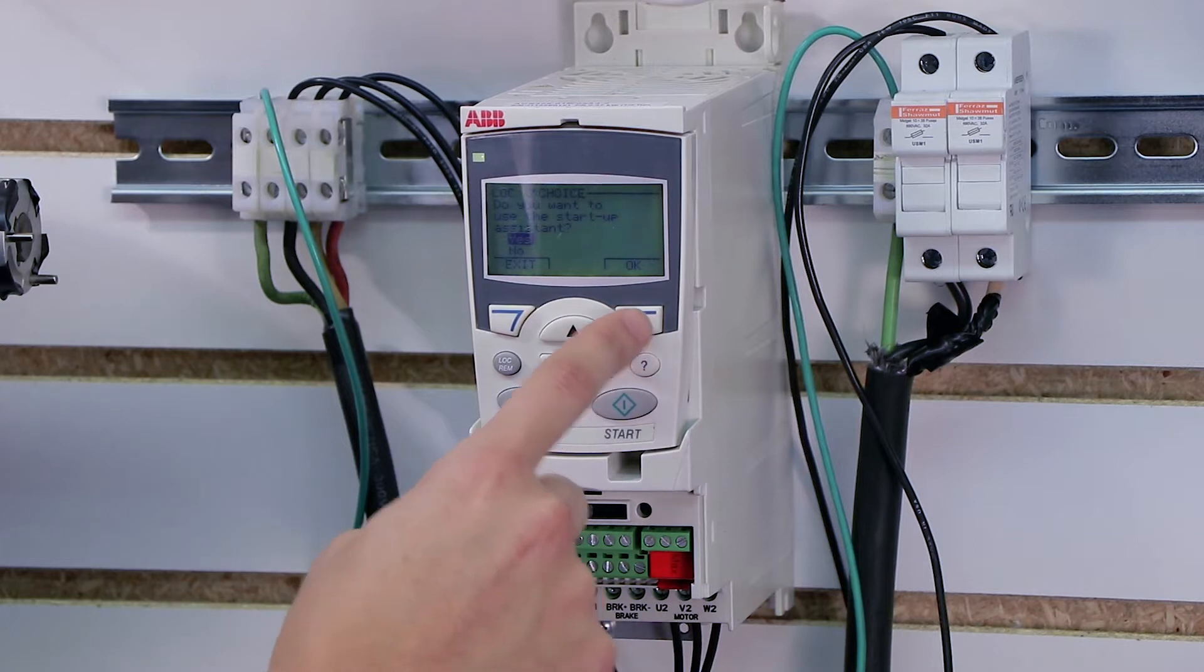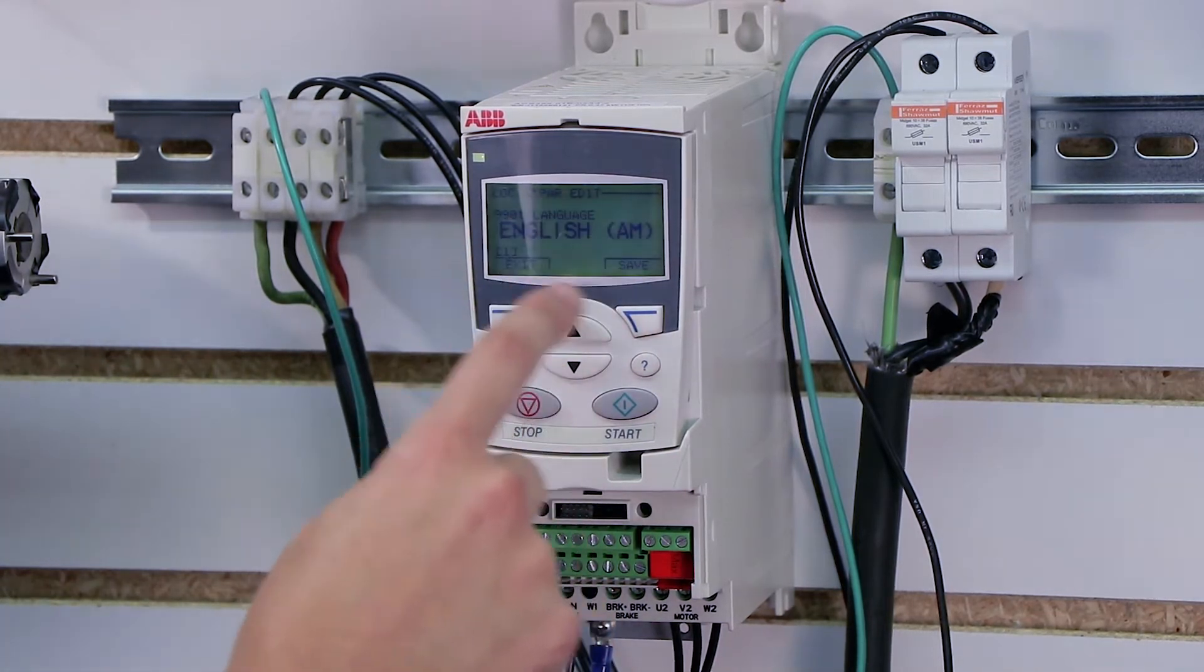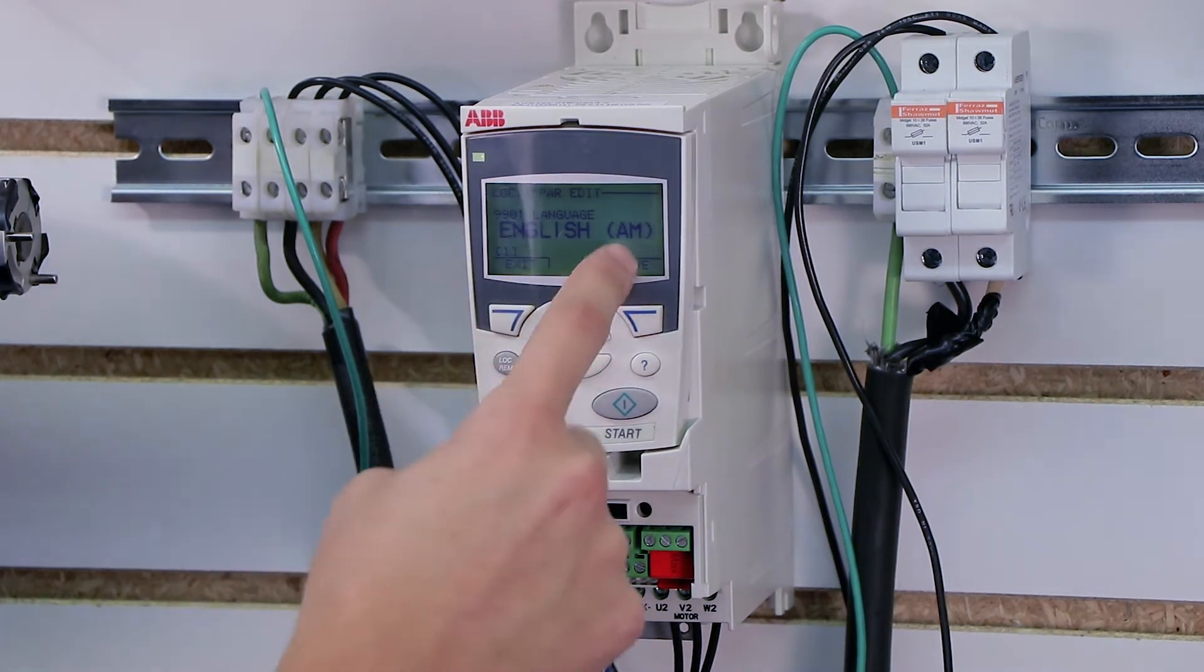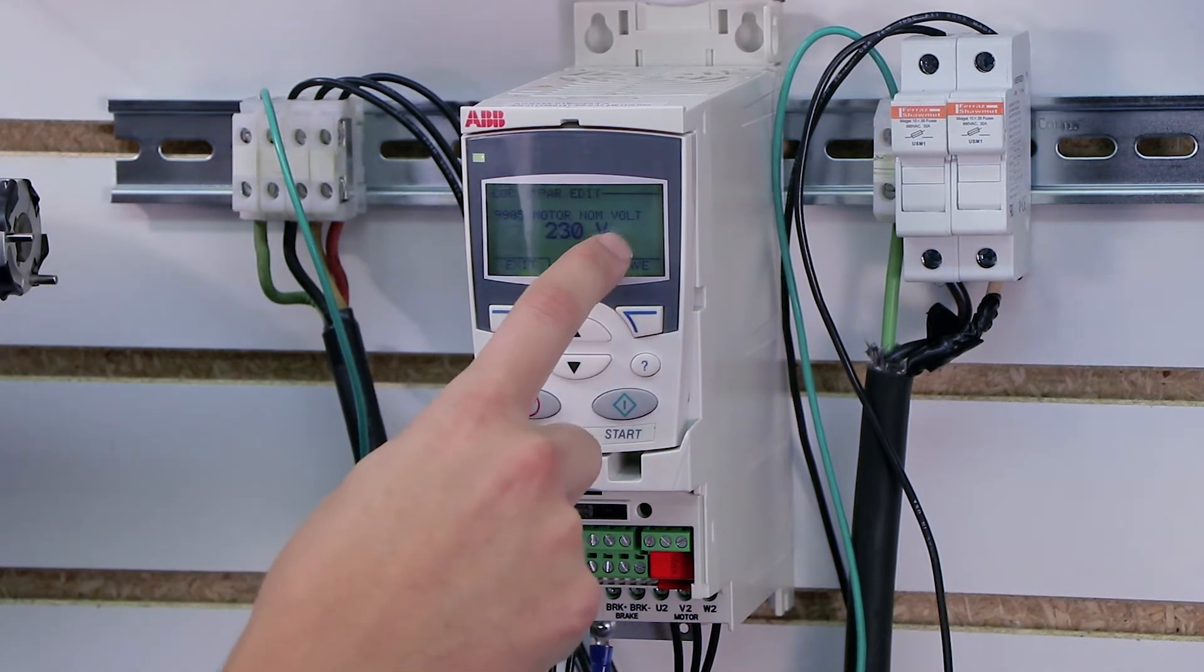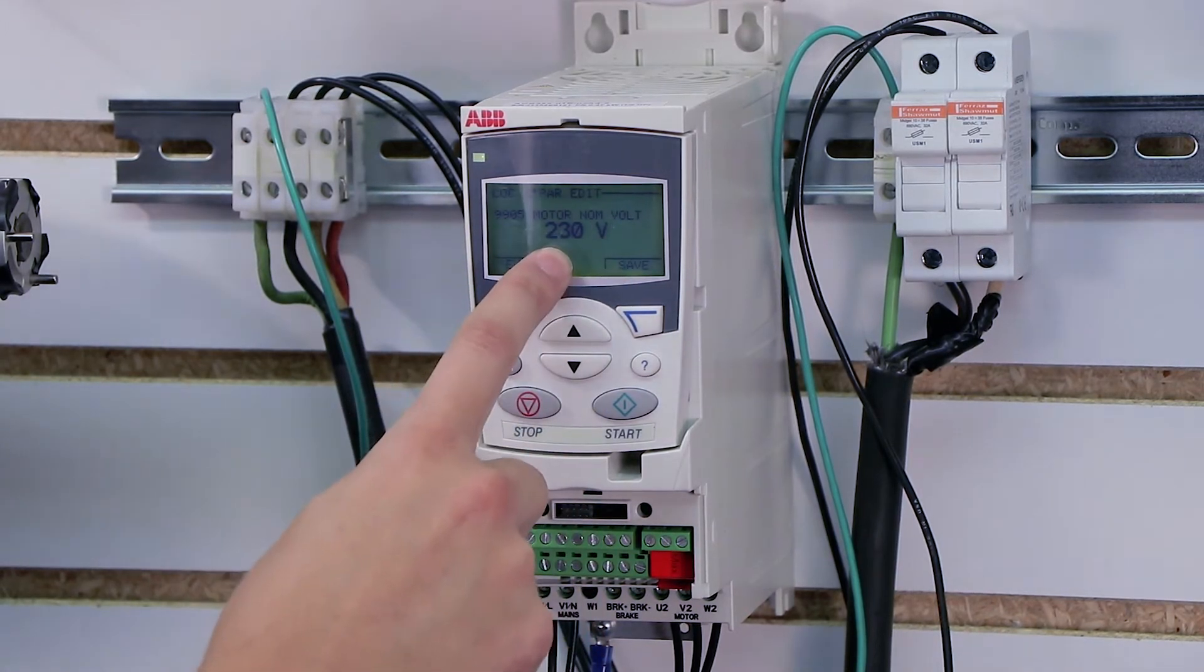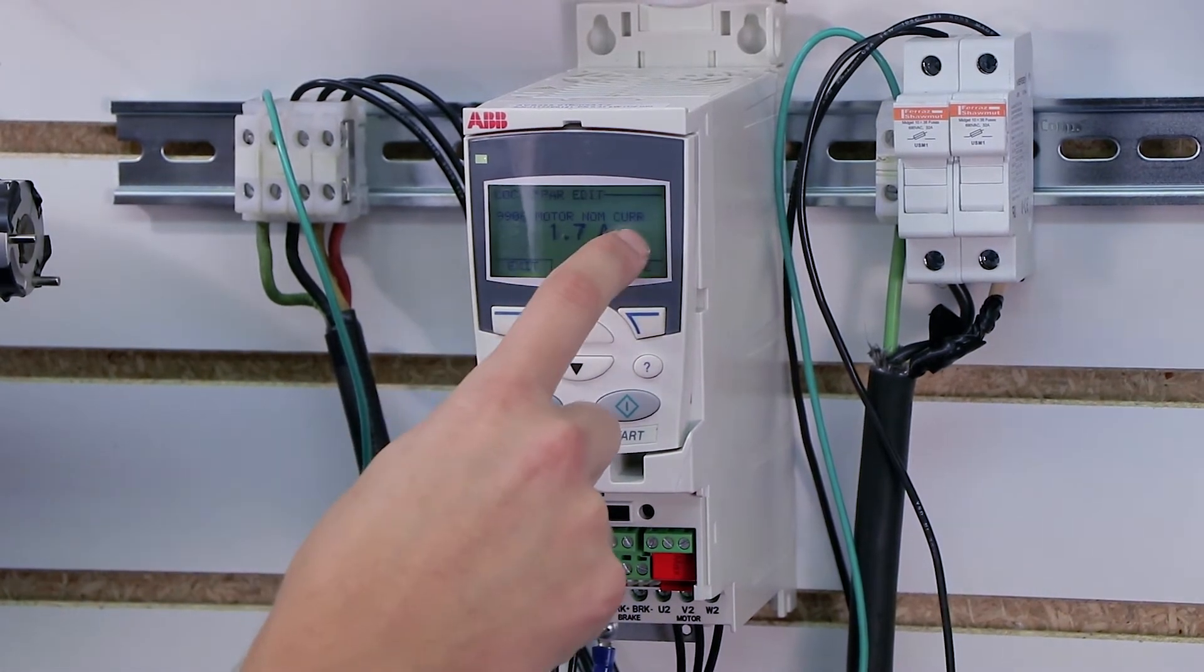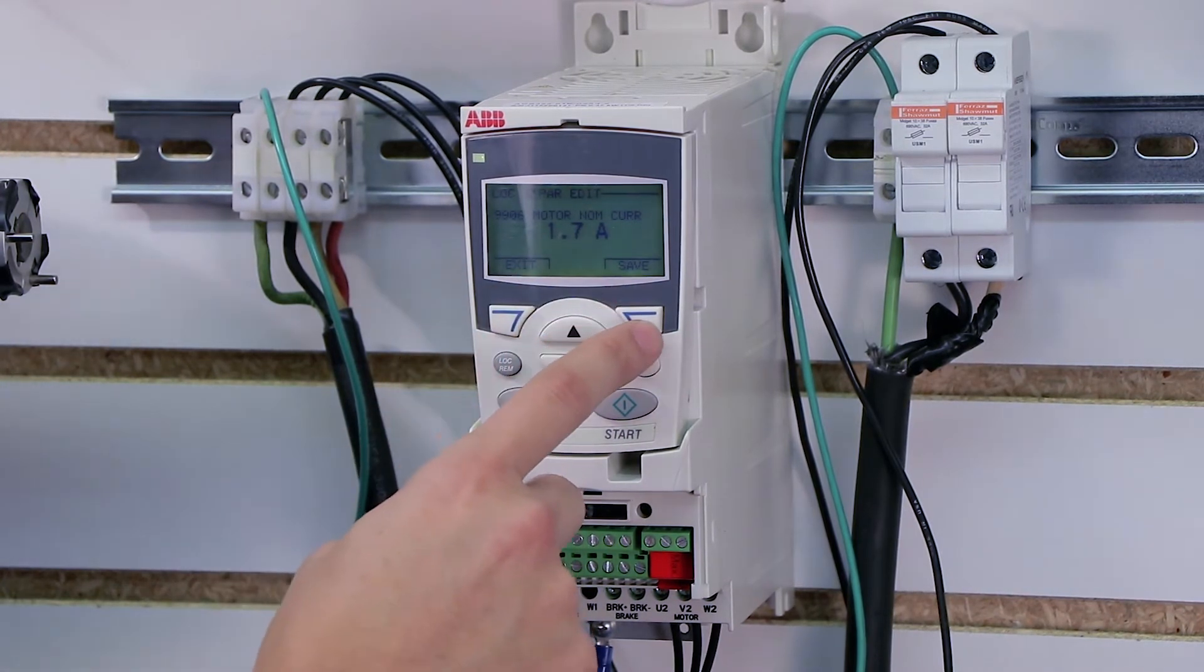And then there's a startup assistant right at the top, and I'm going to press select. It's going to ask me if I want to use the startup assistant, I'm going to say yes, and this is going to walk us through all of the parameters for our basic start-stop. Now for me, obviously, I'm going to choose English as my primary language. The motor nominal voltage, this will be on the nameplate of your motor. Mine is 230 volts. The motor nominal current is also on the nameplate of my motor, and my motor runs 1.7 amps at 230 volts.